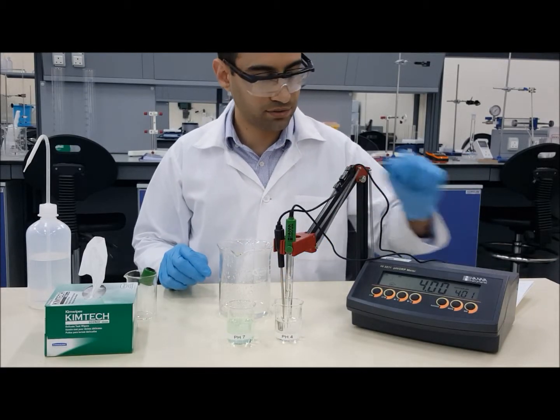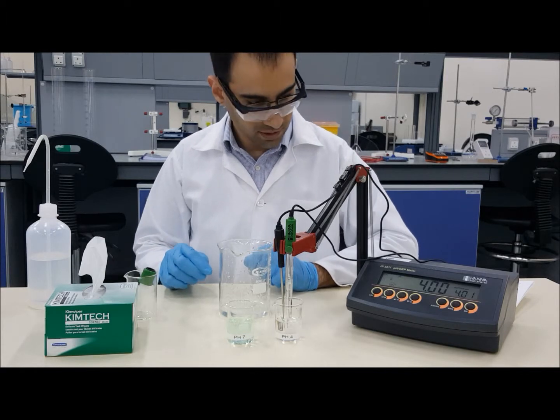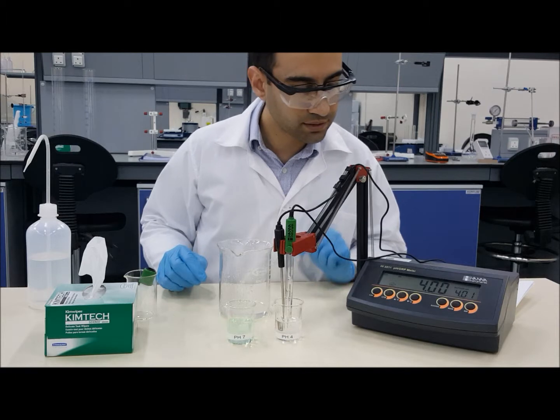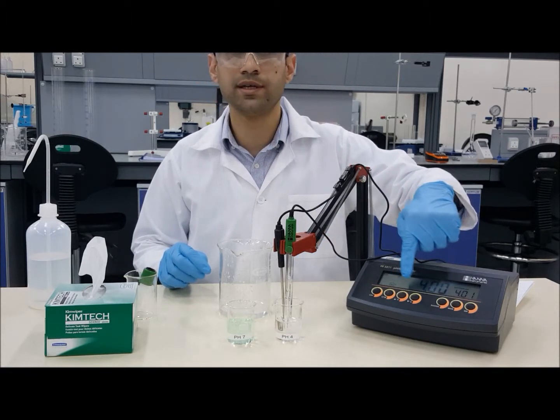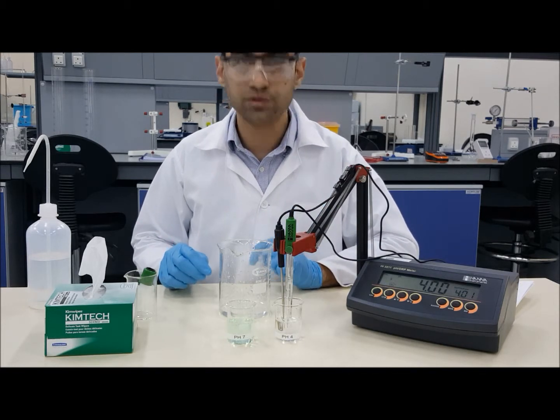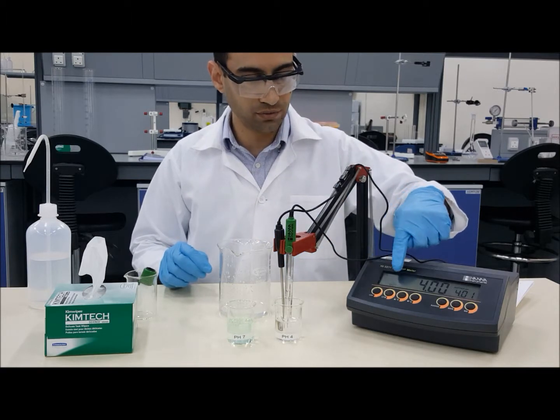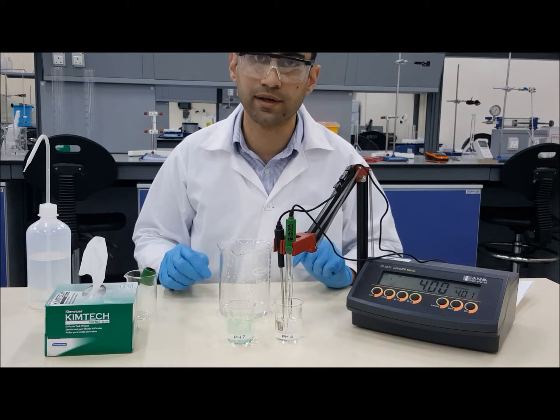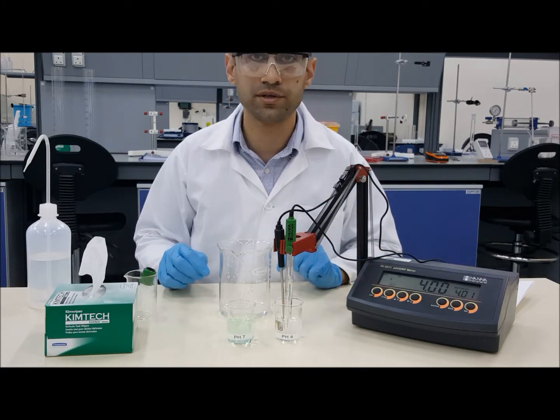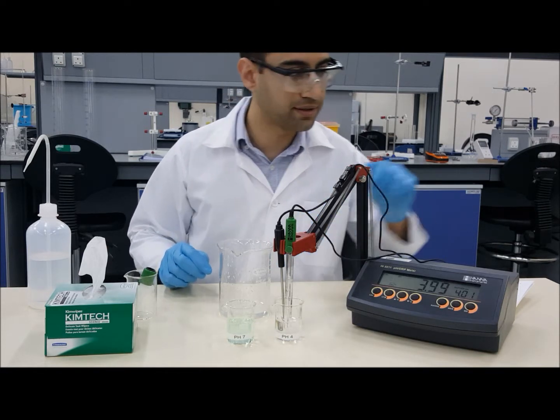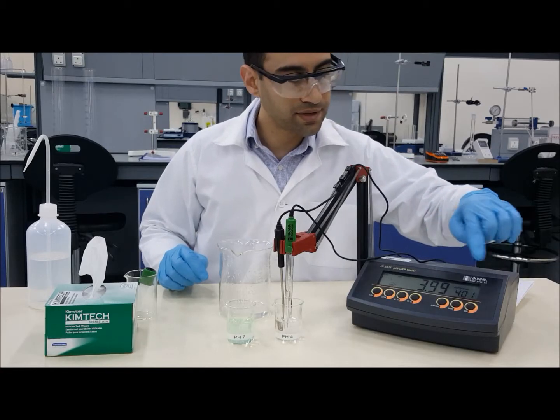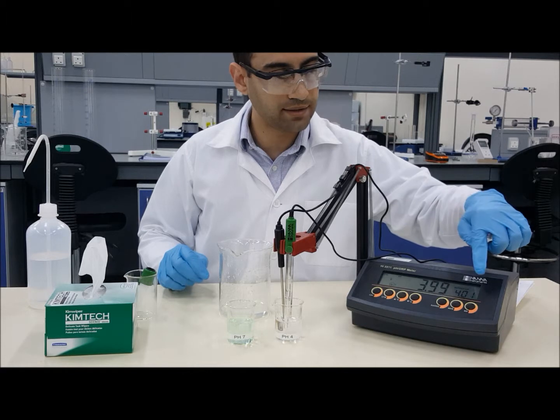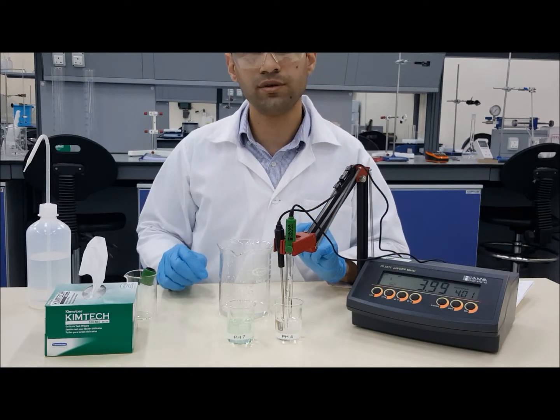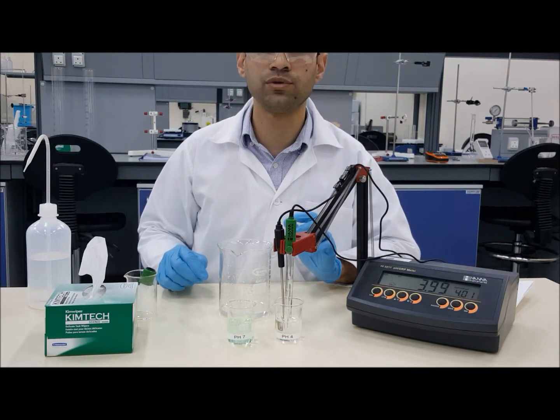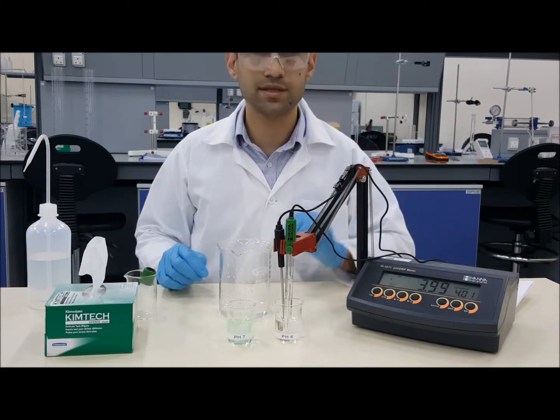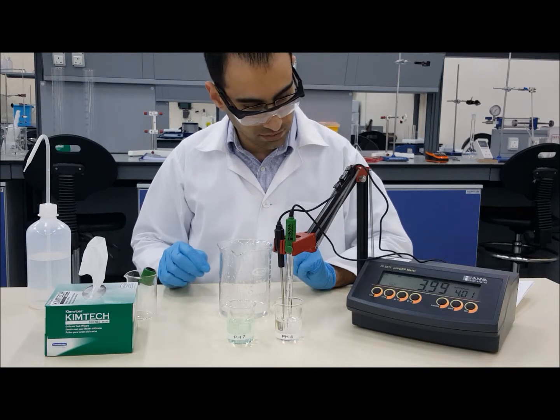In here we are using the Hanna Instruments pH meter HI2211. We can cover these buttons while waiting. We've got temperature up and down, which will be basically to change the temperature value manually or to change the buffer solution if we are in the calibration. The first two, we use them in the calibration. CAL is for entering the calibration procedure. CFM is to confirm measurements, if it's in the calibration or in other cases. These three here are range, memory, and MR. Range is going to change the range of measurement. MEM is for memory, to take a value and store it in the memory, and MR is read memory, which will read a value from the memory stored previously.